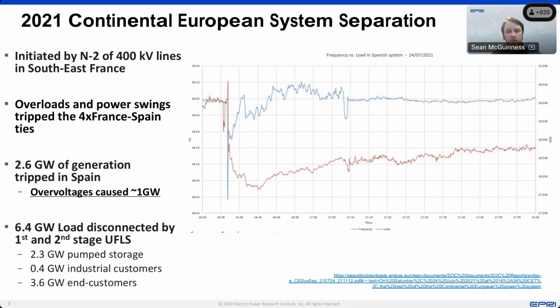In response to all of this, they had first and second stages of their under-frequency load shedding system defense activated. Now, a lot of their load shedding first stage comes from pump storage. So they had about 2.3 gigawatts of pump storage in pumping mode at the time, so they could just trip that off. That helped a lot. Then a number of industrial customers were also disconnected, and about 3.6 gigawatts of end customers were also shed due to conventional UFLS relay tripping. So in response to an N-2, multiple steps of their system defense plan kicked in. It was able to arrest the decline in frequency, and they were able to restore all of the customers within a few hours, and the system survived, and everything operated pretty much as expected from there.